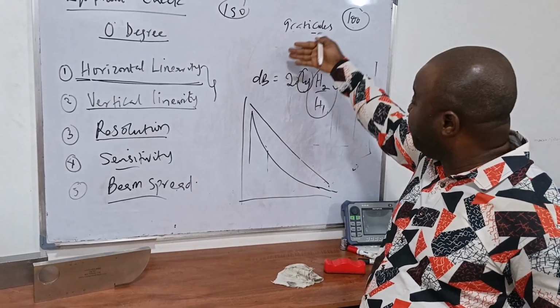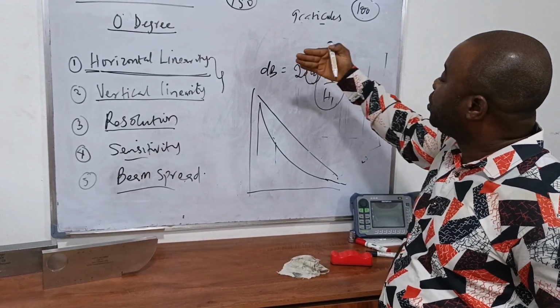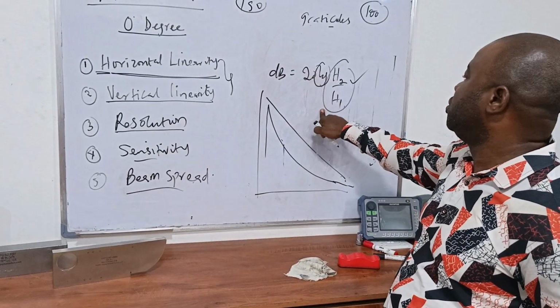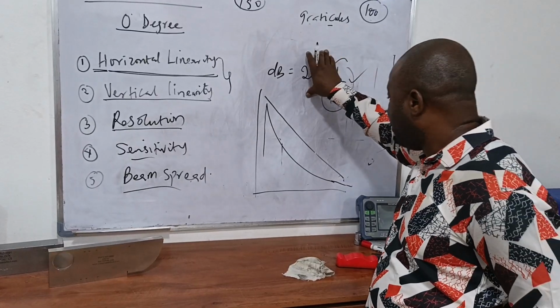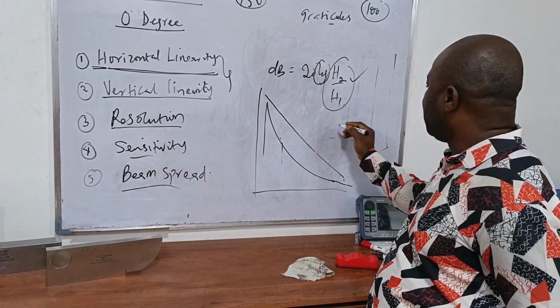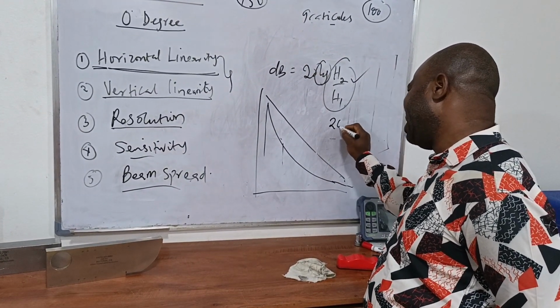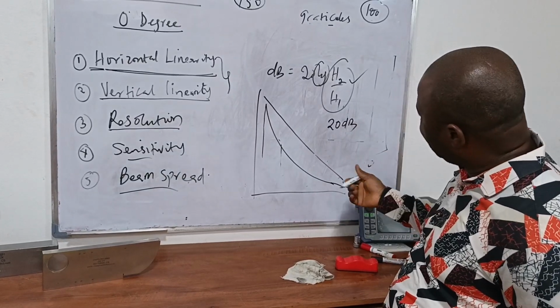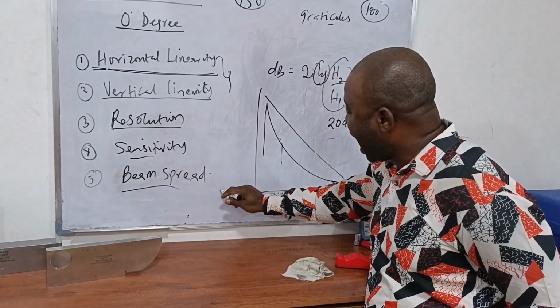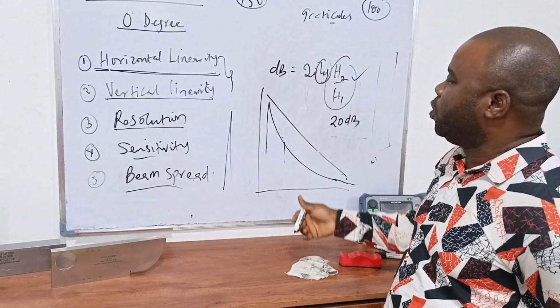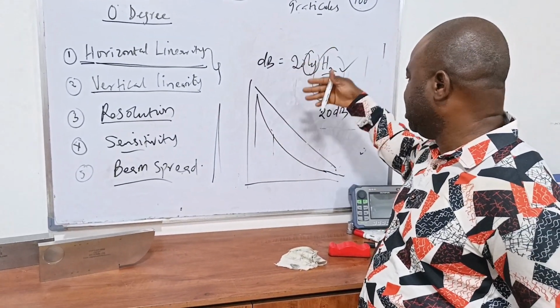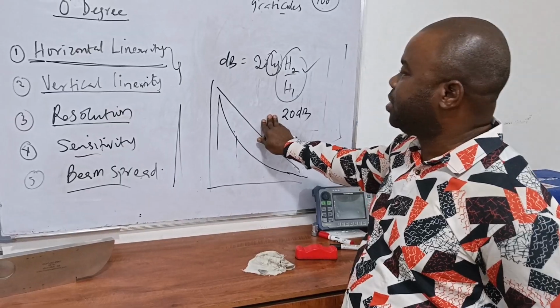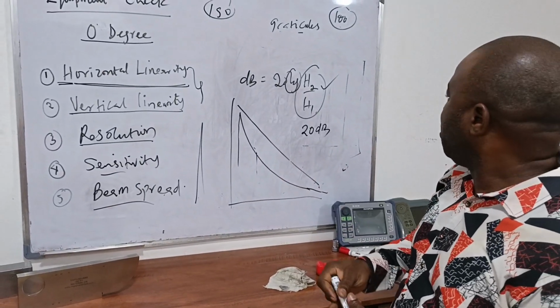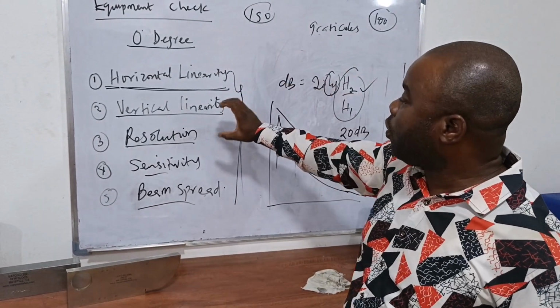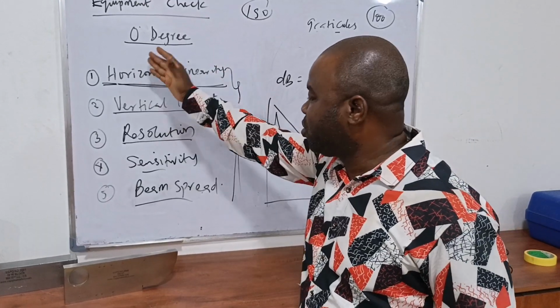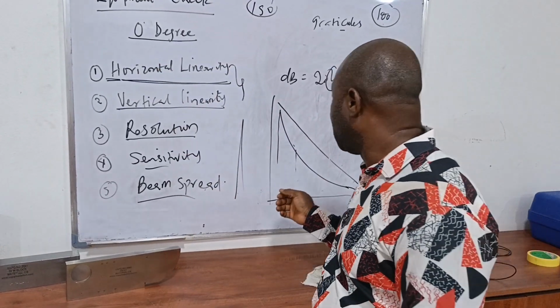What this means is that if you follow this calculation, you see that your dB level will be changing according to this formula. For example, we know that if I have, let's say, 20 dB as my gain value, if I increase it by 6 dB, my screen amplitude is supposed to go up. So we'll practically look at how we check for this. Because of time and the length of this video, we are going to practicalize this first thing before we go to the next one.